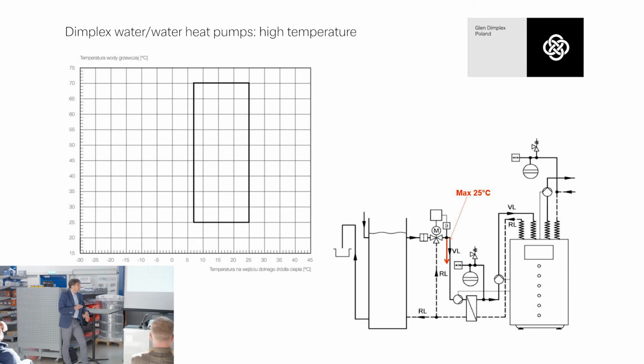It is important to be in the range. If we have heat recovering from sources with a temperature higher than 25 degrees, we need to use a special protection setup. Mostly we use an additional three-way valve with an actuator, a mixing valve, which stabilizes the temperature on the inlet to the heat pump.